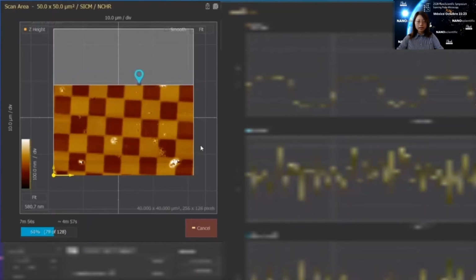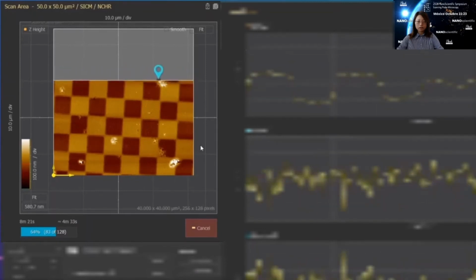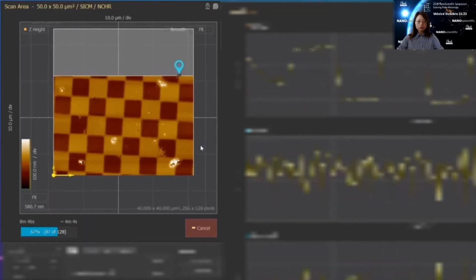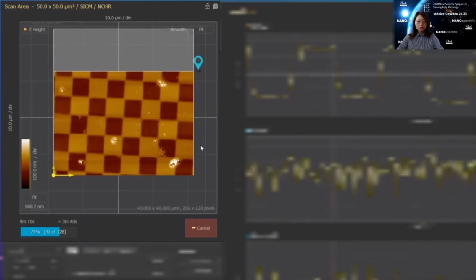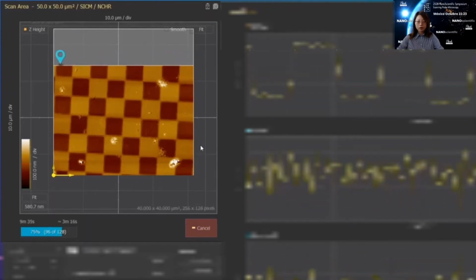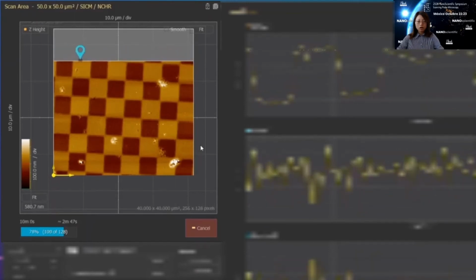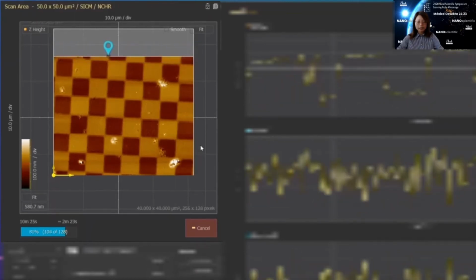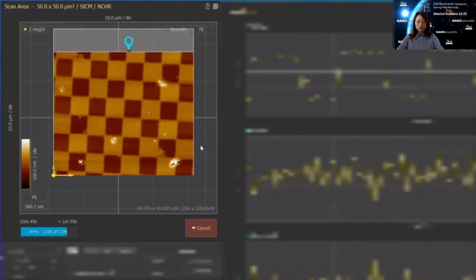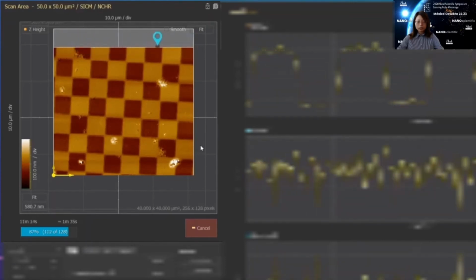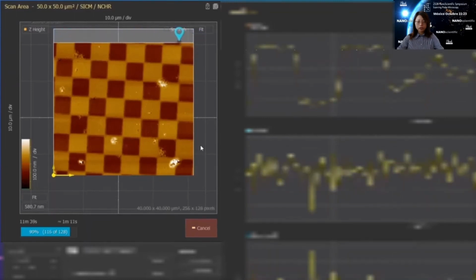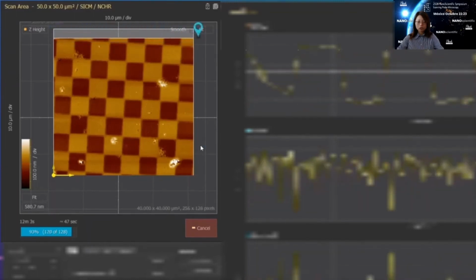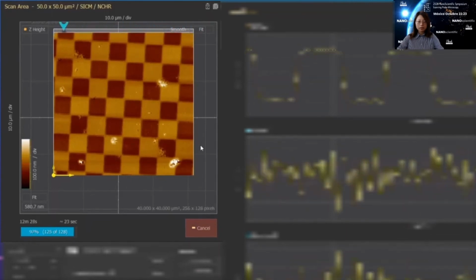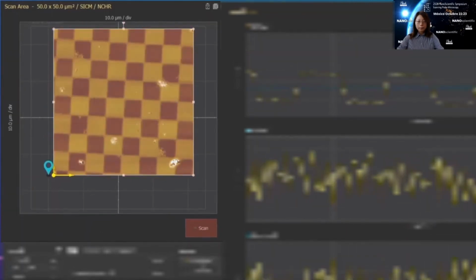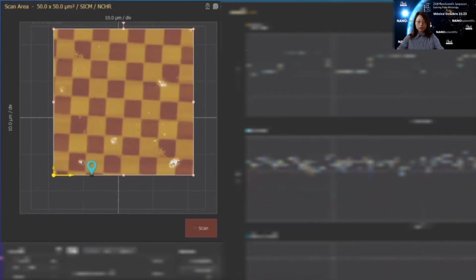Other useful SmartScan features are available, such as image offset and automatic tip lifting to move to other sample locations. The image taken here is a 40 micron by 40 micron scan, taken in skip scan mode, which reduces image time by half by skipping the retrace scan. The image is 256 pixels by 128 pixels, and the pattern features about 150 nanometers in height with a 10 micron pitch. In this case, the total image time is approximately 12 minutes, but the setup and image process in this video is shown at 8 times faster than the actual speed.